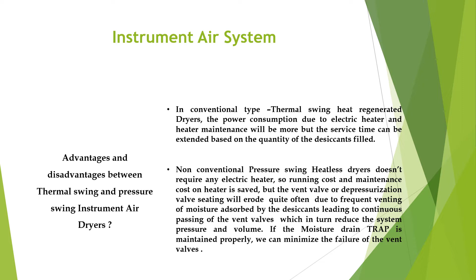In non-conventional pressure swing heatless dryer, it does not require any electric heater, so running costs and maintenance costs on heater are saved. But the vent valve or depressurization valve seating will erode quite often due to frequent venting of moisture adsorbed by the desiccants, leading to continuous passing of the vent valves, which in turn reduces the system pressure and volume. If the moisture drain trap is maintained properly, we can minimize the failure of the vent valves.